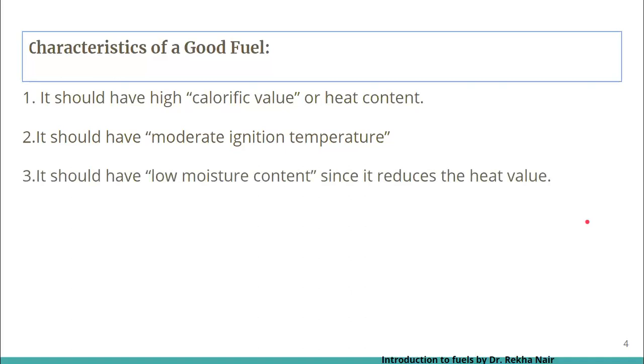It should have low moisture content because it reduces the heat value. It takes away an appreciable amount of liberated heat in the form of latent heat of vaporization and increases the transport cost. Surface moisture causes difficulty in handling the solid fuel. Presence of 5–10% moisture is desirable because it produces a uniform fuel bed and also less amount of fly ash.